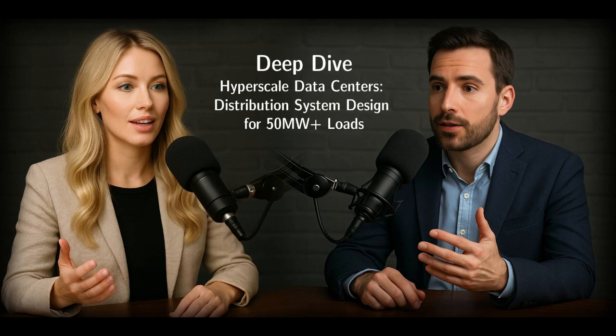Well, traditionally, we always assumed single customers would have relatively small loads, 5 megawatts, maybe 15 megawatts max. It was spread out. Exactly. Loads were spread across lots of different feeders, and you got this huge benefit from diversity. Not everyone peaks at the same time. Yeah. A typical 12.47 kilovolt feeder might serve, say, 200 to 400 customers. Okay. Their combined peak might be 15, maybe 20 megawatts. And the load factor, how much energy they use compared to their peak, maybe 60, 70%.